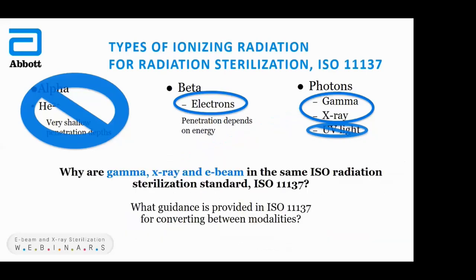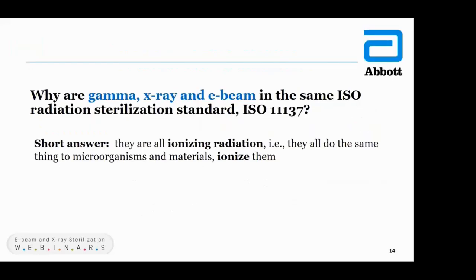So this leads to the question, why are gamma, X-ray, and E-beam in the same ISO radiation sterilization standard 11137? The second part of this section will be on what guidance is provided in the standard for converting between modalities.